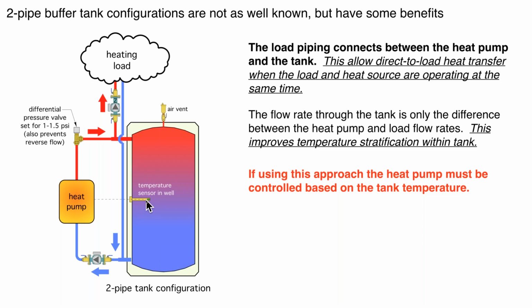That's a 10-degree differential. That could be the logic. Or it could be an outdoor reset controller. Outdoor reset control is basically going to change the temperature, the on and off temperature for the heat pump in response to how cold it is outside. So on a mild day, we might let the buffer tank temperature go down to, let's say, 80 degrees, and then turn the heat pump on and run the tank temperature up to maybe 90 degrees. And the benefit of that, again, is the lower we can keep the water temperature back to the heat pump, the higher the COP is going to be.